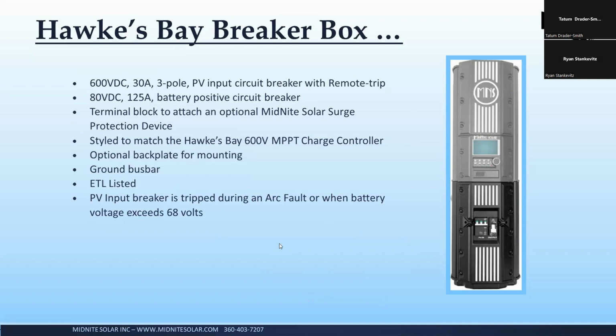Like, we have product fail. Everybody does. It's just part of the way it is. So that breaker on the left-hand side in that picture is remote trip. And internal to the charge controller is an analog circuit that's completely independent of everything in the charge controller. And if the battery voltage exceeds 68 volts, it trips that breaker instantly. So that's just a last ditch fail safe before we have any kind of catastrophic thermal event with the lithium battery from overcharging. Just kind of a nice safety feature.